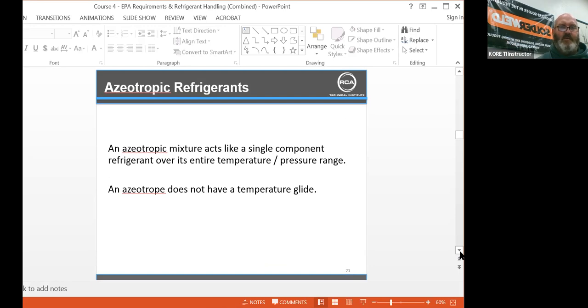Azeotropic refrigerants. An azeotropic refrigerant mixture acts like a single compound refrigerant over its entire temperature pressure range. An azeotrope does not have a temperature glide.